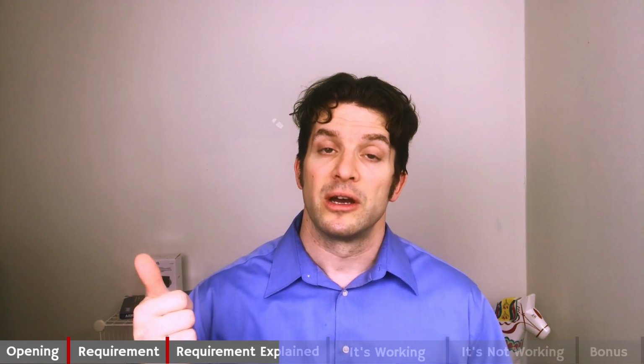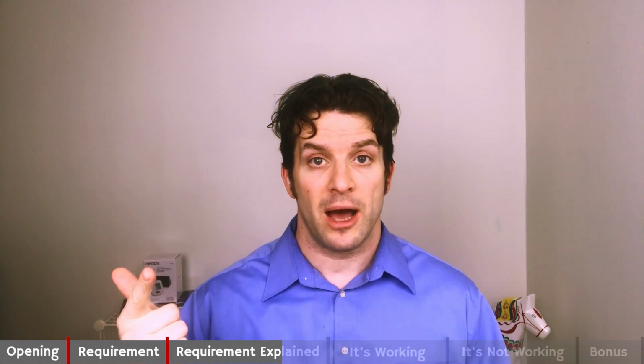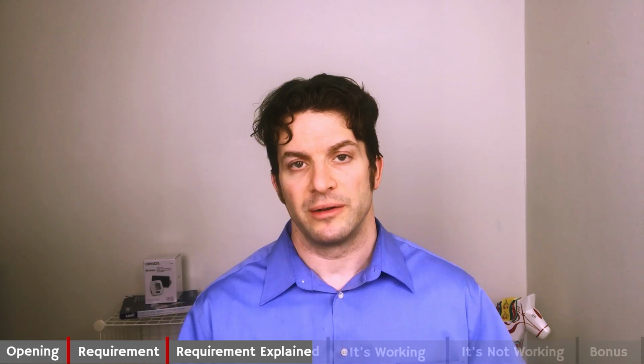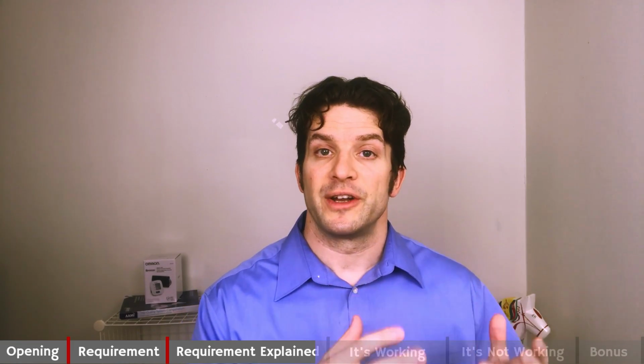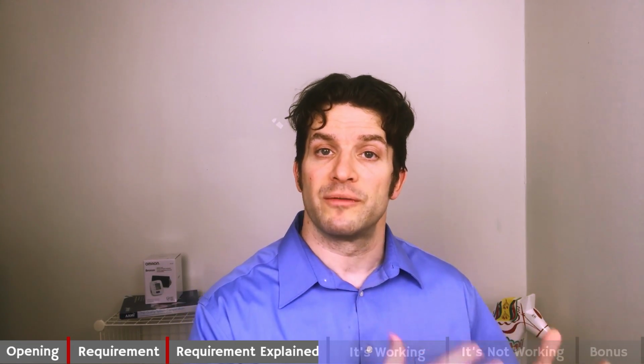I have to have a rework work instruction. I have to train my operators to that rework work instruction. I have to review the rework itself for any potential adverse effect that rework may have on my product. And then finally, once my rework is complete, I have to re-inspect the product to its original acceptance criteria. Once all that work is done, I will have a completed nonconformance record. Your DHRs for your finished medical devices have to capture all nonconformances that occurred during the manufacturing process.